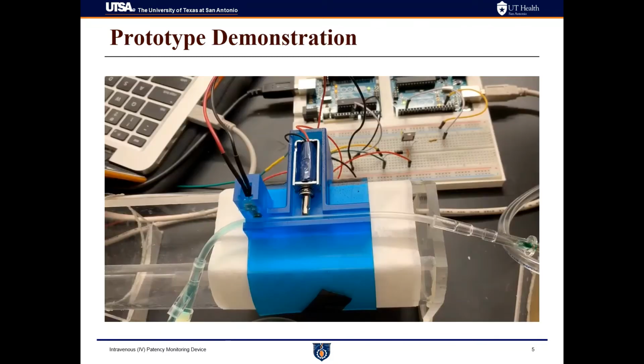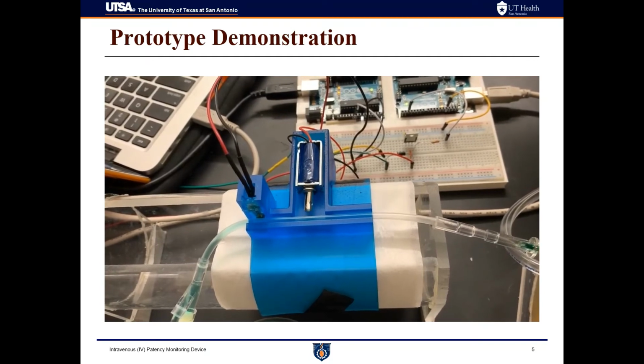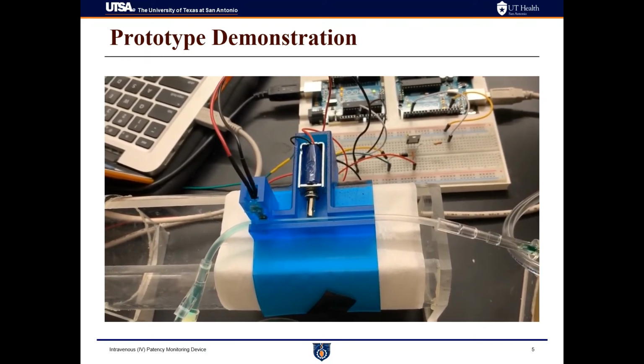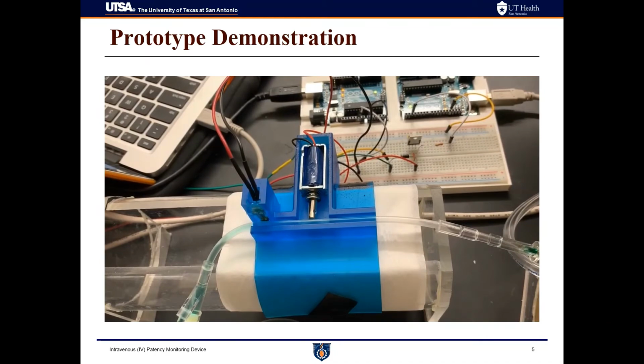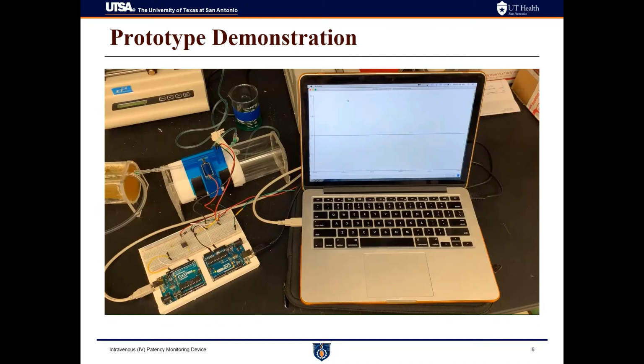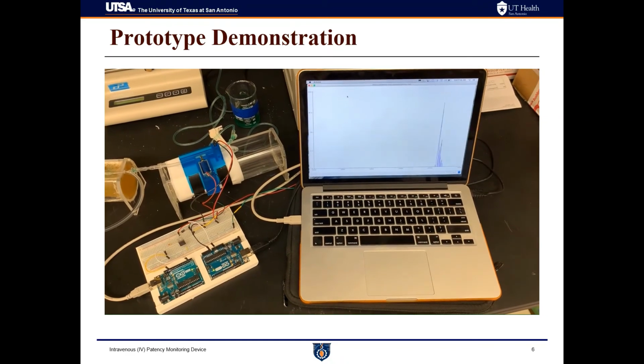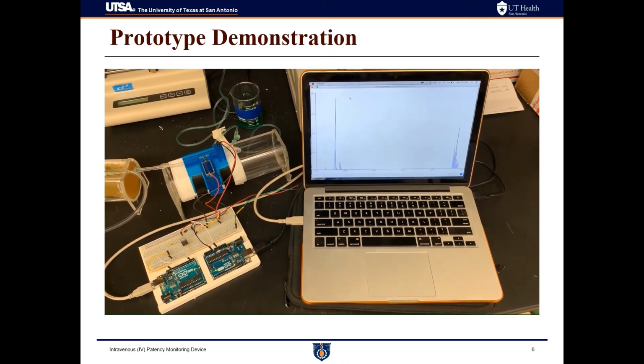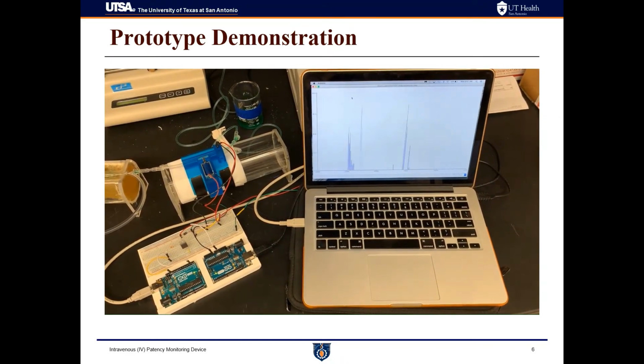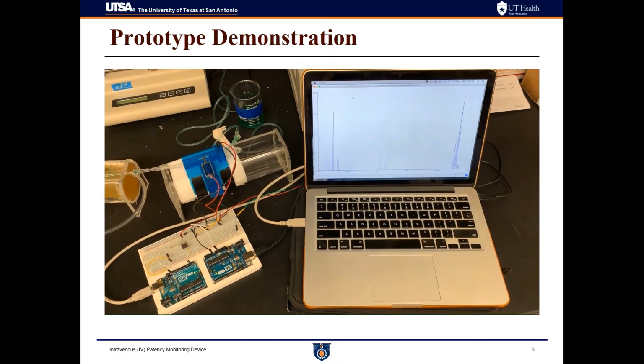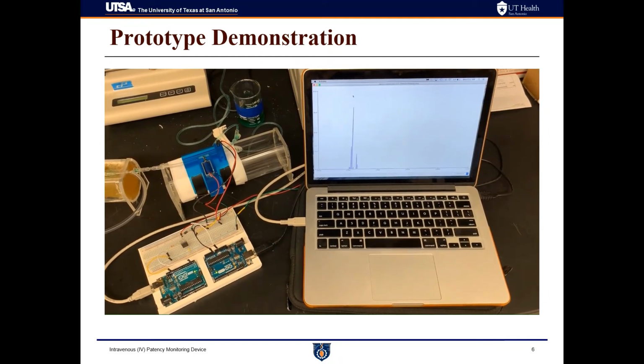This is a demonstration of how our device works. The linear solenoid fires and impacts the IV line, sending vibrations through the fluid. There's a vibration sensor to the left of the linear solenoid that detects the vibrations within the IV line. This video shows the signal being generated by the vibration sensor as the linear solenoid impacts the line. As you can see, we're sampling at a very high frequency in order to capture the vibrations.